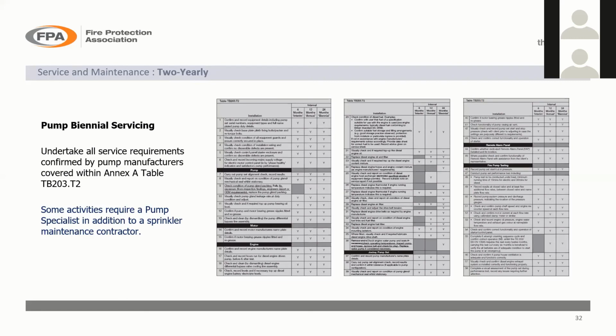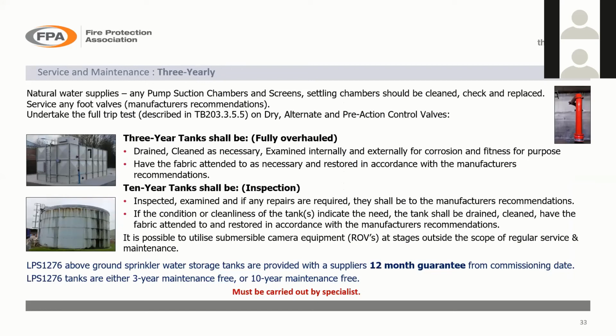Some maintenance contractors have the specialist knowledge, but if you are the system user, what you need to do is look for the competency and training records. So there are 3 yearly checks, and there are going to be 5 yearly and 10 yearly coming up. On this particular page, you've got 3 years and 5 years. If you've got a 3-year tank or a 10-year tank, your 3-year tank would need to be drained and cleaned as necessary. The difference between the 3-year and 10-year is that when you purchase the tanks at the time of installation, you'll purchase either a 3-year tank or a 10-year tank. A 3-year tank is free from maintenance for 3 years. In broad terms, obviously look into the rules and get the full definition, but a 10-year one is free from maintenance for 10 years. So they're slightly different.